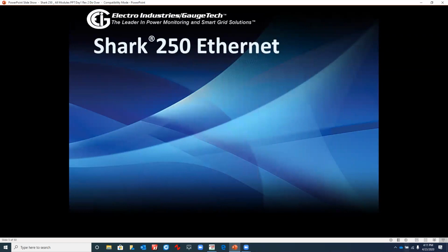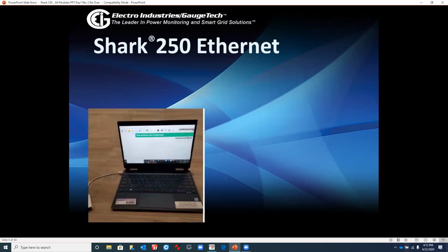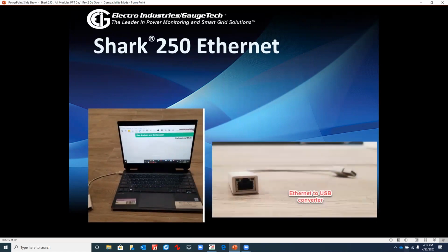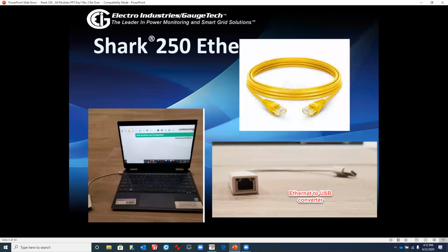So the next option is the Shark 250 Ethernet connection. This is basically a laptop computer. You'll need a USB to Ethernet converter and an Ethernet patch cable. And of course, the Ethernet option allows you to have 12 simultaneous Modbus TCP connections to the meter. And the default IP address for the Shark 250 is 10.0.0.2.